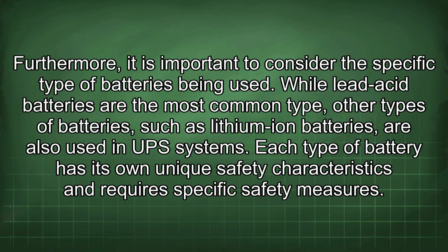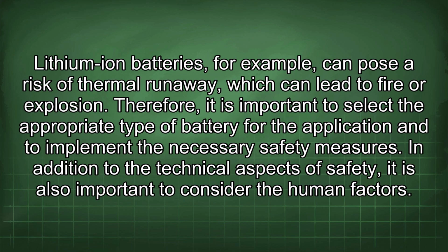Furthermore, it is important to consider the specific type of batteries being used. While lead-acid batteries are the most common type, other types of batteries, such as lithium-ion batteries, are also used in UPS systems. Each type of battery has its own unique safety characteristics and requires specific safety measures. Lithium-ion batteries, for example, can pose a risk of thermal runaway, which can lead to fire or explosion. Therefore, it is important to select the appropriate type of battery for the application and to implement the necessary safety measures.